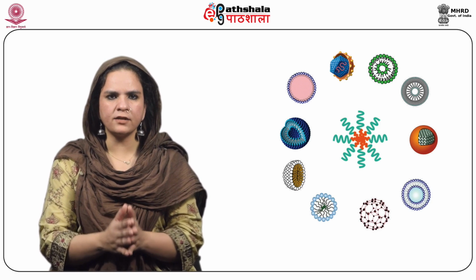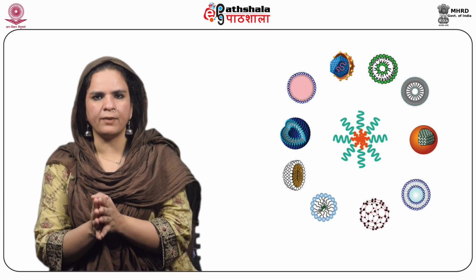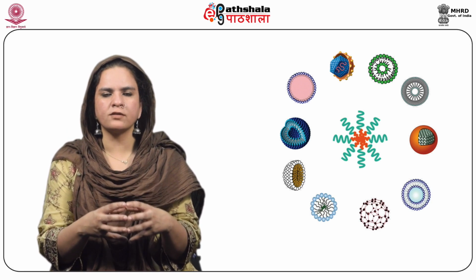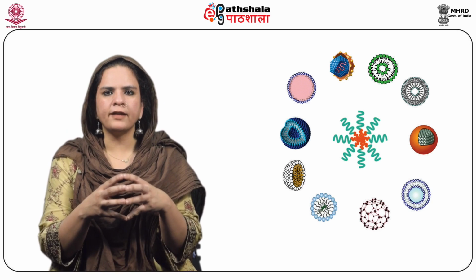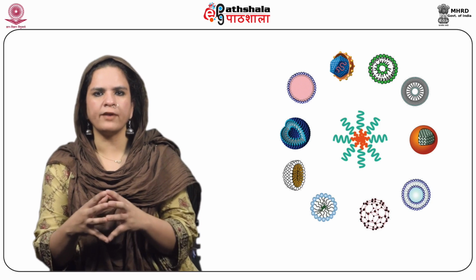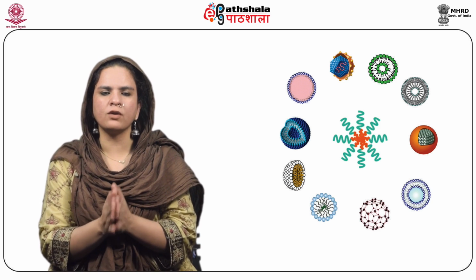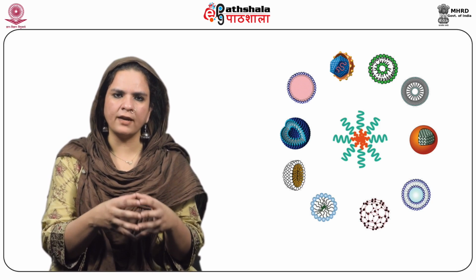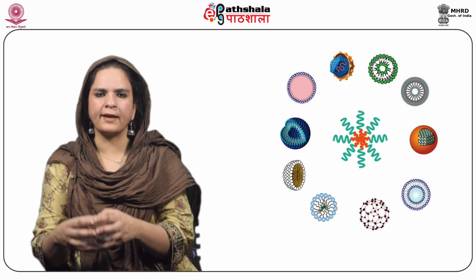If a high concentration of drug is delivered at the implantation site, maybe because of the burst effect, maybe because of some other scenario, there is always a chance of adverse reactions due to this local high concentration. And sometimes very difficult situations can arise where tissue necrosis can happen.